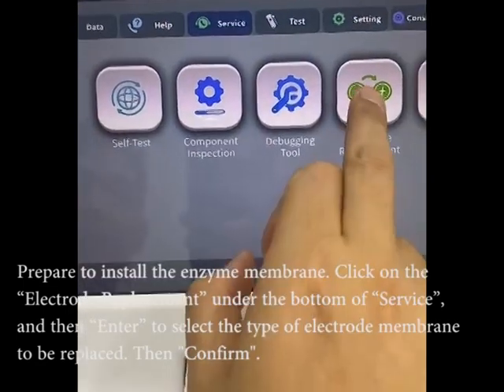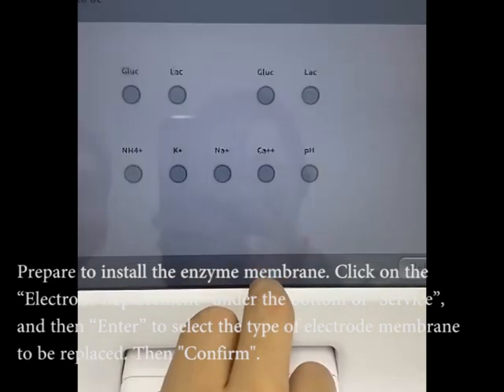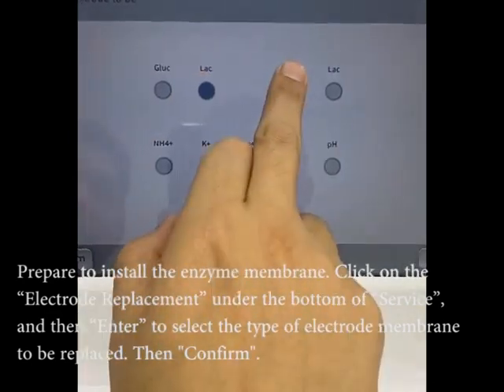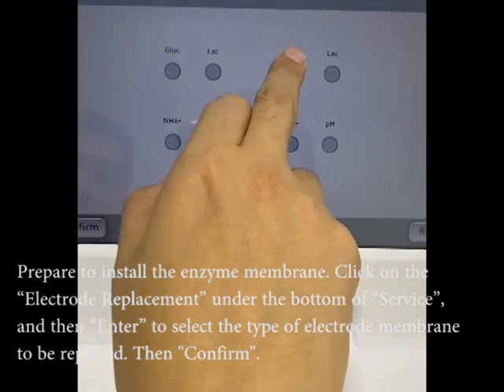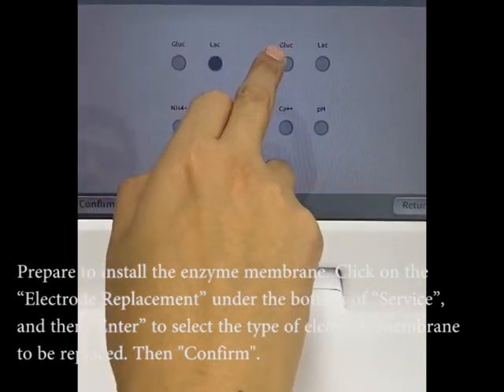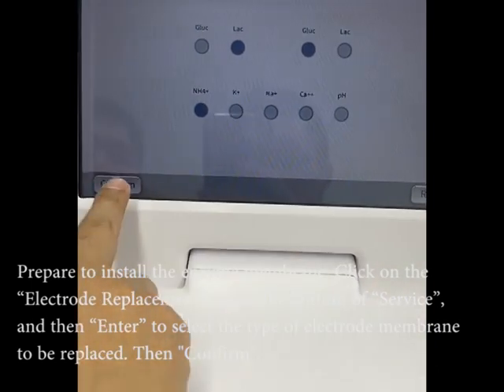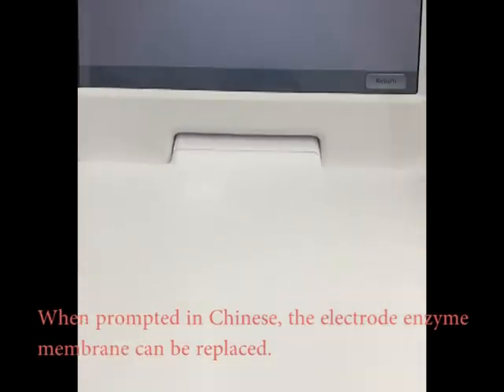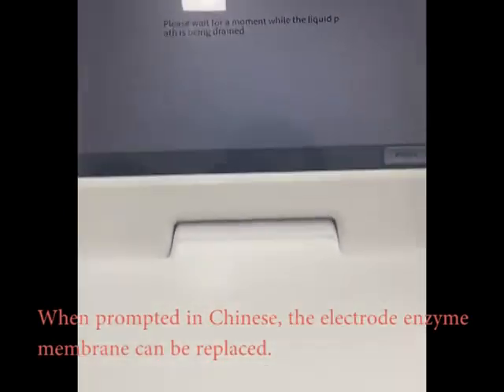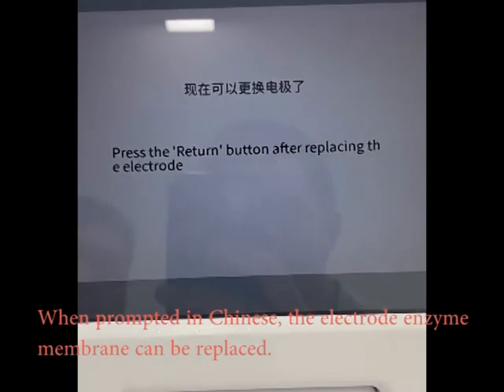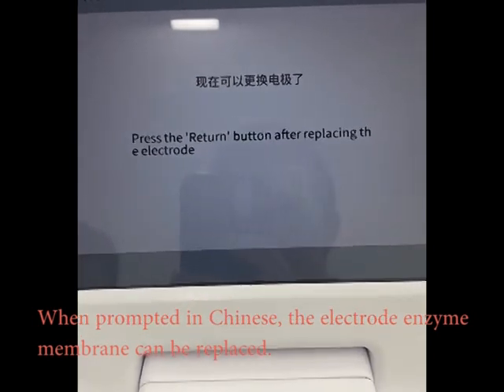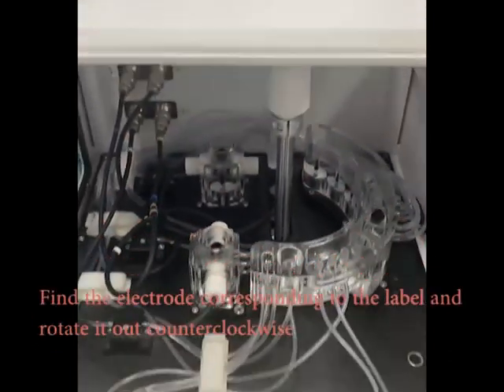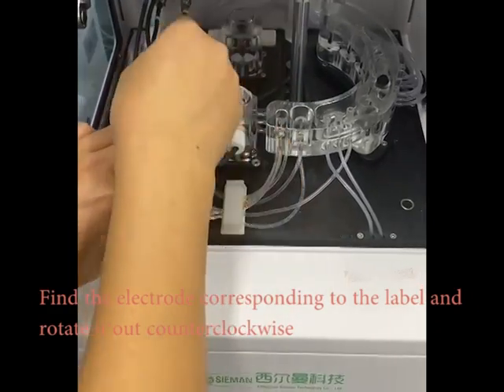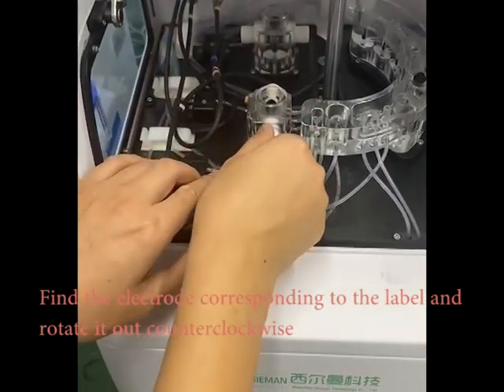Click on Electrode Replacement at the bottom of Service, and then Enter to select the type of electrode membrane to be replaced. Then confirm. When prompted in Chinese, the electrode enzyme membrane can be replaced. Find the electrode corresponding to the label and rotate it out counterclockwise.